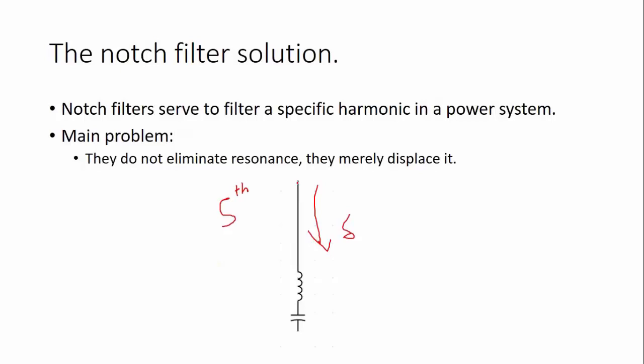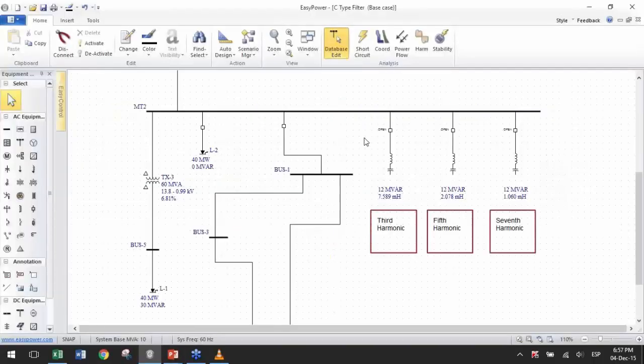Now, these filters are very good when you just want to filter 1 or 2 harmonics. But when you want to filter a lot of harmonics, especially in the lower end of the spectrum, let's say second or third harmonic, these filters present a very important problem: they don't eliminate resonance, they just displace it. Now, to see what I mean, let's go here to EasyPower.